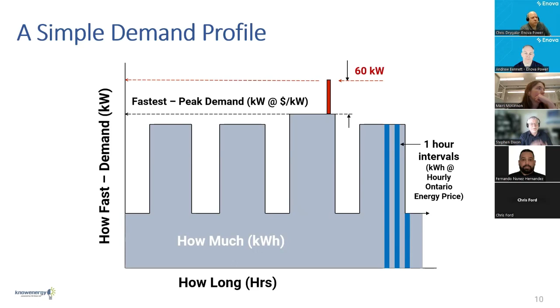So the problem with the bills this gentleman was looking at was that he didn't realize he pushed 60 kilowatts up on peak in that second month. January was the blue, February is what we added. The 60 kilowatts for 15 minutes at 10 cents a kilowatt hour - that's $1.50. But to get that additional 60 kilowatts of demand there, at $11 a kilowatt, which is about what it is within an Enova rate, is about $660.